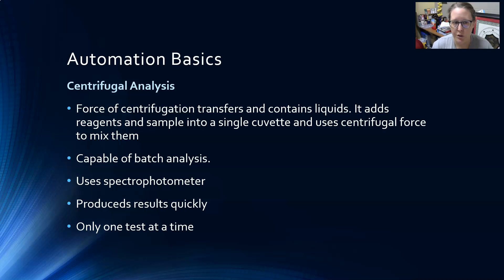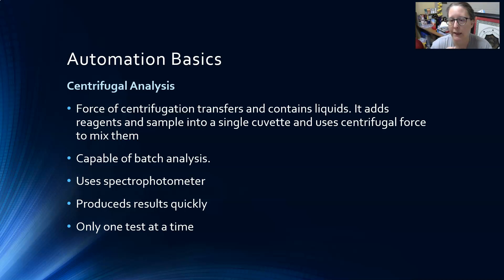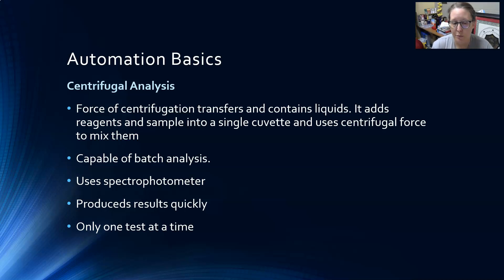In centrifugal analysis, centrifugal force transfers and mixes liquids — reagents and samples are added into a single unit and centrifugal force mixes them. A good recent example used in smaller labs is the Abbott Piccolo, which uses a small rotor cartridge. You place the sample in the middle, and centrifugal force separates the plasma and distributes it into reagent chambers where the reactions occur. It is capable of batch analysis — you load your sample and select a panel, and that's the only thing that runs at that time. It uses a spectrophotometer to read reactions and produces results quickly, but only runs one panel per cartridge at a time.